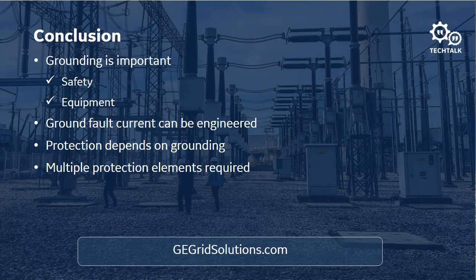So there is a time rating for that resistor, and that's what happens when we size these resistors. We make sure that for the maximum amount of time that fault current is allowed to be on the system, it's not going to damage that resistor. So as I said, it can get expensive to size that resistor properly to not only carry the fault current, but to carry it for the time that we need it to. That's a very good question.